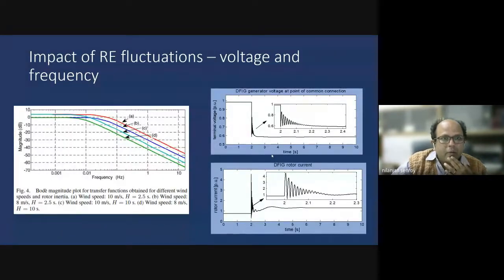Let's just quickly look at how the voltage and the frequency of the grid are affected by the fluctuations in renewable energy. Here I'm showing two graphs, obtained by simulating a wind turbine subjected to a low voltage situation. On the right, you can see that when the DFIG, the doubly fed induction generator, voltage drops, the rotor current rises tremendously, to about 4 times the rated current. You can see that 400% rated current is seen in the DFIG. This kind of behavior requires that the DFIGs be disconnected during low voltage situations.